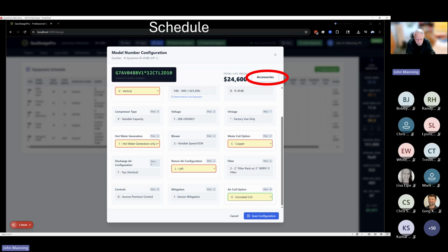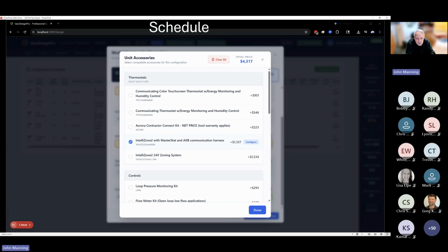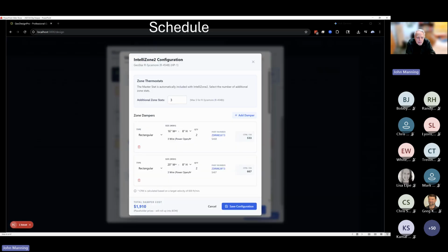You can move on and click on accessories, and I'll discuss one of the accessories. Let's say you want the IntelliZone 2, which is available on Water Furnace and Geostar products. And I just saw the Climate Master new zoning package, and that in itself is a pretty exciting product. But if you want zoning, it also gives you the ability to configure that zoning. And by that, I mean you get to stipulate how many extra zones above and beyond one. So how many extra zone stats do you want? Oh, three. So a total of 4 zones. You can also add dampers. You can specify the size of the damper, whether you want a 3-wire or 2-wire damper, the quantity, and the program will give you the part number, the list price, and an idea of the CFM that's appropriate for that damper. So you go through this process.